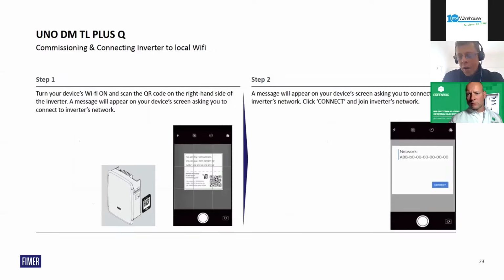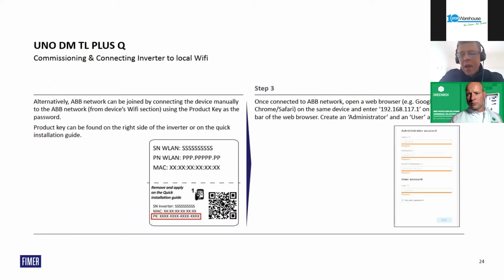So I'll just go over the steps of commissioning the Uno DM Plus Q. It's super simple. It only takes a few minutes to commission one. As I mentioned before, there's a QR code on the side of the inverter that you can scan and connect to the inverter. It will ask for a password. The password is a product key labeled on the side of the inverter. So you just punch in this product key with the hyphens as seen on the label and connect to the inverter. The first thing you'll see is a page pop up, administrator account, user account.